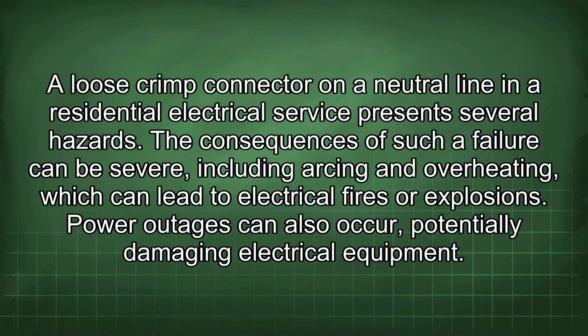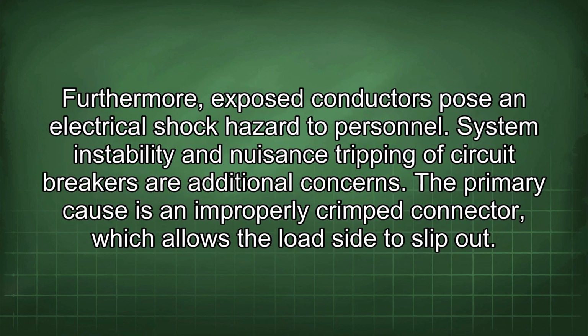A loose crimp connector on a neutral line in a residential electrical service presents several hazards. The consequences of such a failure can be severe, including arcing and overheating, which can lead to electrical fires or explosions. Power outages can also occur, potentially damaging electrical equipment. Furthermore, exposed conductors pose an electrical shock hazard to personnel.